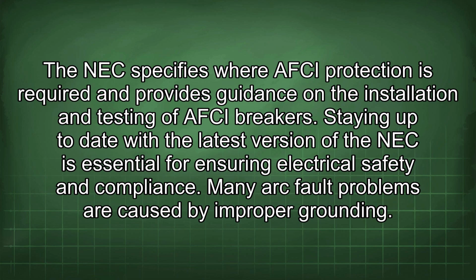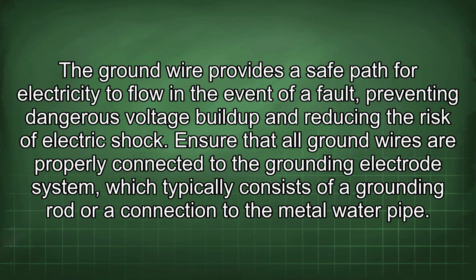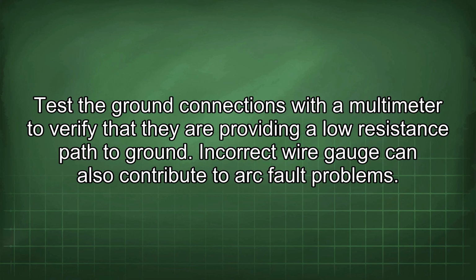Many arc fault problems are caused by improper grounding. The ground wire provides a safe path for electricity to flow in the event of a fault, preventing dangerous voltage buildup and reducing the risk of electric shock. Ensure that all ground wires are properly connected to the grounding electrode system, which typically consists of a grounding rod or a connection to the metal water pipe. Test the ground connections with a multimeter to verify that they are providing a low resistance path to ground.